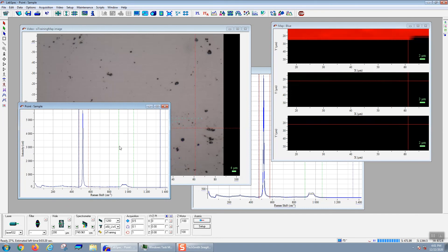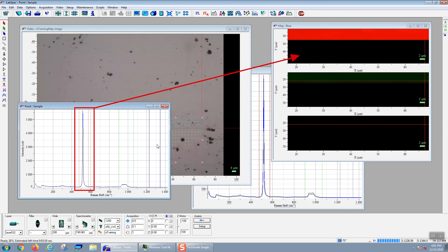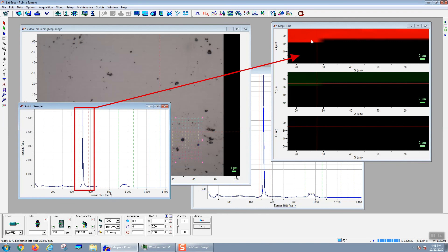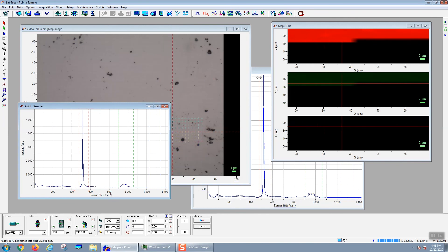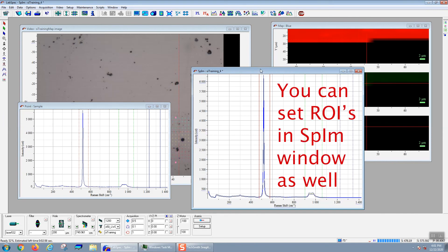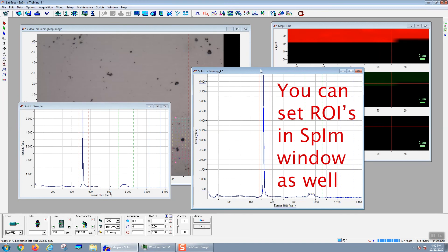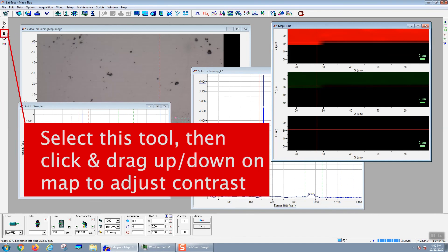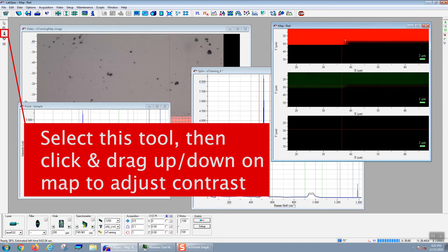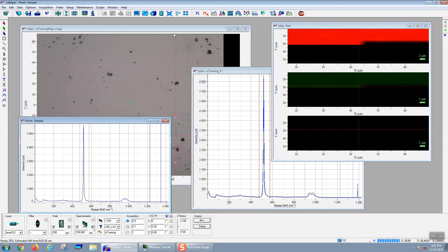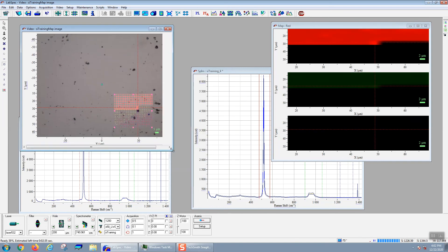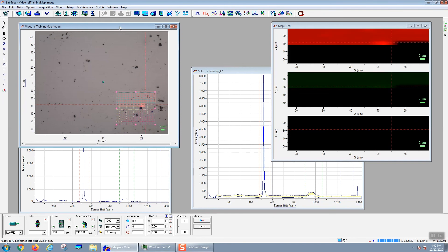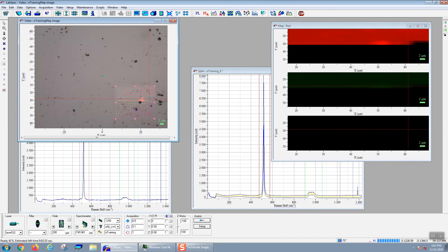The map will give you the integrated area underneath these curves in that region of interest. So the red region of interest would give me the integrated area of this big 520 peak. As your map is filling in, you might want to play around with the brightness and the contrast. You can do this either in the format and scale scaling section, or you can click on the map and select this funny up down icon. What this icon means is that it will change the limits of your intensities so that you can adjust the brightness and contrast. You're going to click on the map and then drag up or down to make the map brighter or darker. In this way, you can adjust the contrast a little bit more so that it's aesthetically pleasing or gives you the information you want to know. This is particularly useful when you're overlaying your map on top of your bright field image.